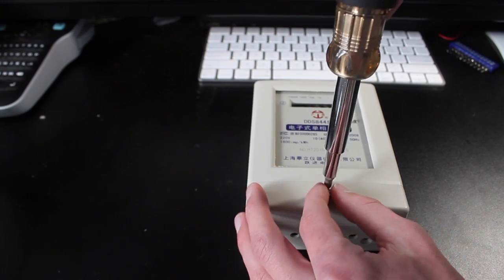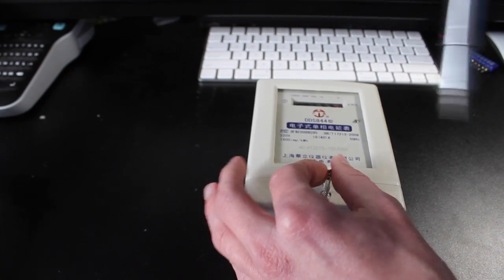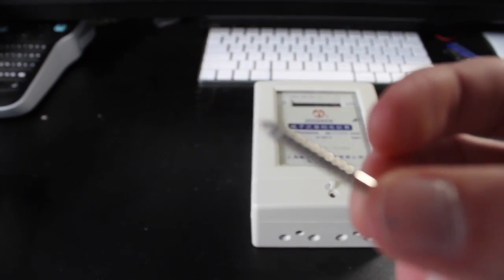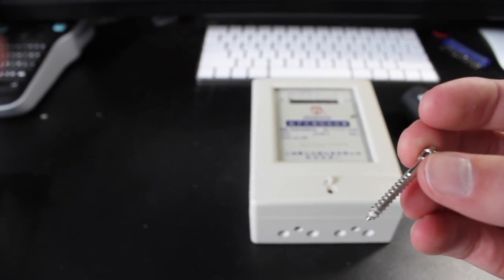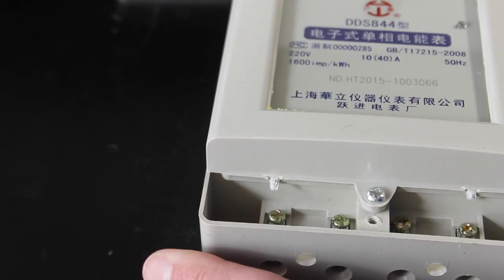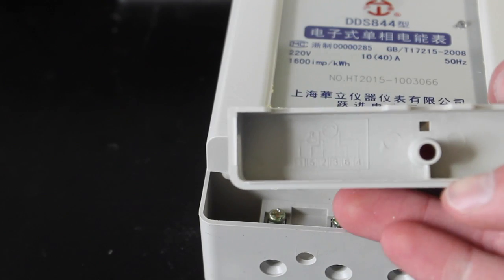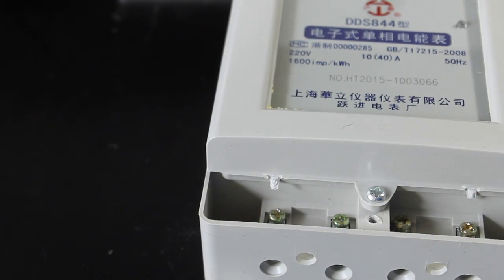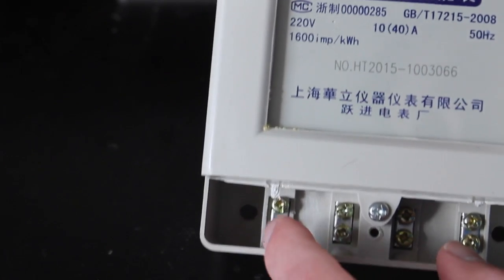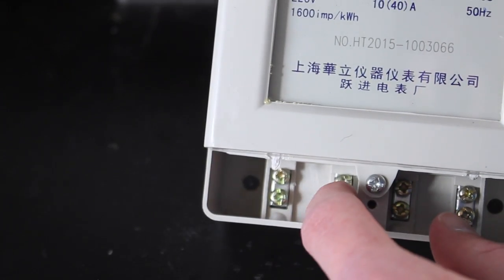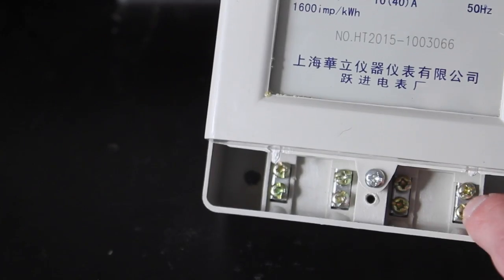There's my screwdriver. So remove the terminal cover. As you can see, that looks like a straight up drywall screw. Actually, I should zoom in. But yeah, it looks like a drywall screw. Quite funny. But anyway, the terminal cover comes off. And your schematic for wiring. The camera's not going to pick it up well, but it's phase line, phase load, neutral line, neutral load.